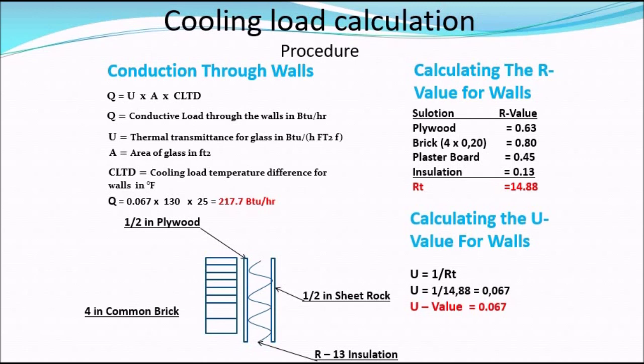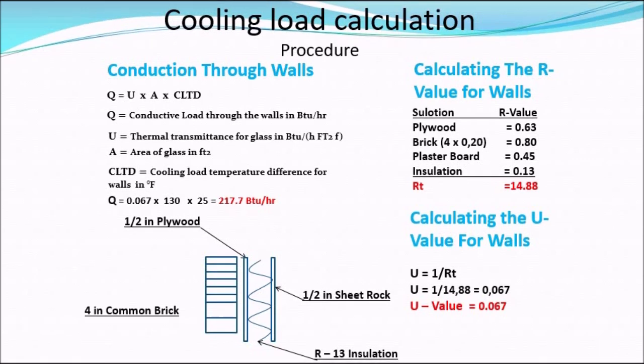To calculate the conduction load through the walls, we first have to find the U-value, and to do that we need the R-value. The R-value is the resistance to the flow of heat — heat always flows from hot to cold, and a higher temperature difference increases heat flow. When resistance is higher, the amount of heat flowing through the materials is lower. The U-value is simply the reciprocal of the R-value and describes how fast heat flows through a material.